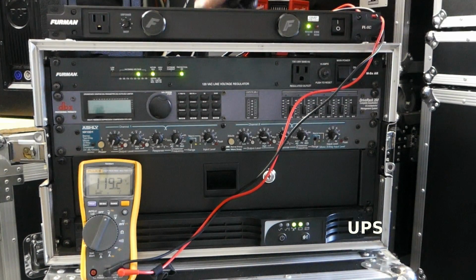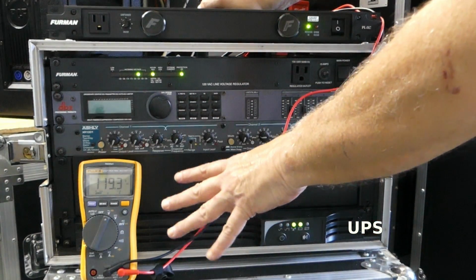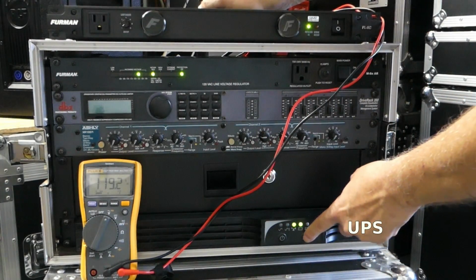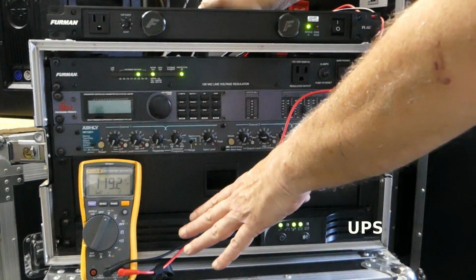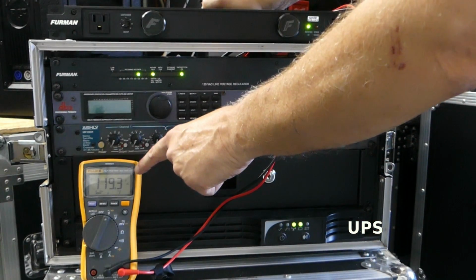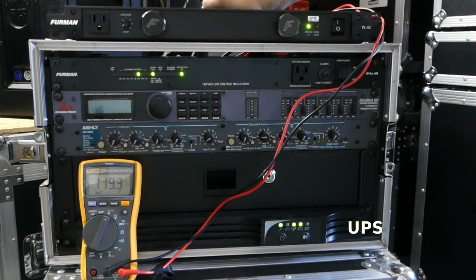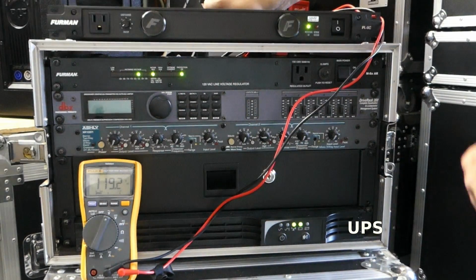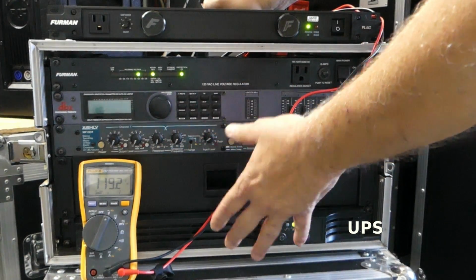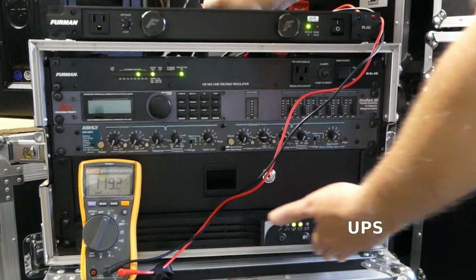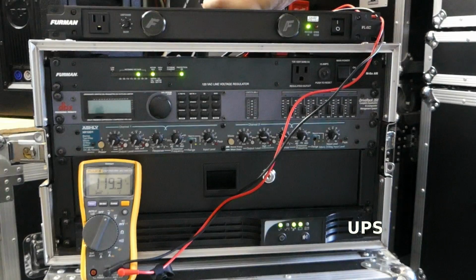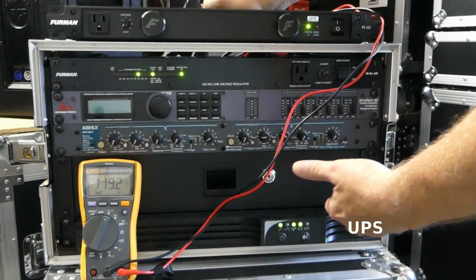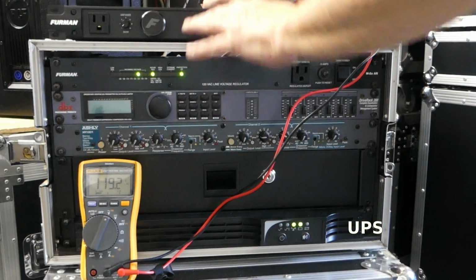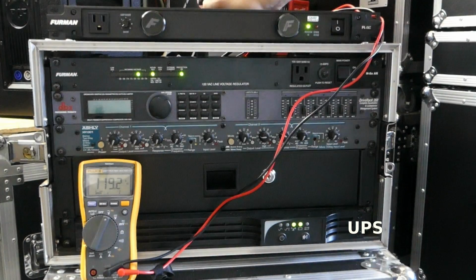All right, and this is where the UPS is quite a bit different. We're all under UPS power. So even though it's lost power, it's not putting out 125 volts anymore. It's putting out about 119 volts, which is more accurate of the kind of power you would want to see. A UPS does not regulate the power that it's sending out the outlets. It's acting just like a PDU until you lose power.